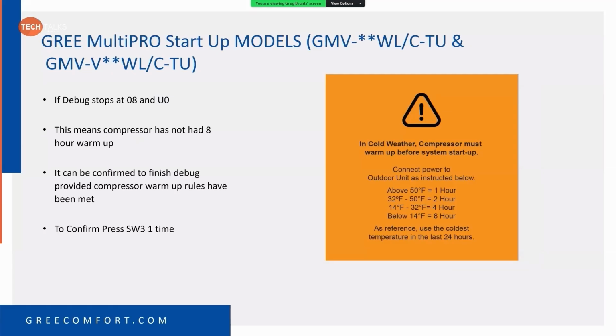The other thing is the 8-hour warm-up. Since that video was produced, we came up with some new rules. If your debug stops at 08 U0 that James talked about in that video, this means that the compressor has not had the 8-hour warm-up that's required. As you can see from my PowerPoint, you can override it, but we want you to override it with rules, so that we don't end up with a damaged compressor.